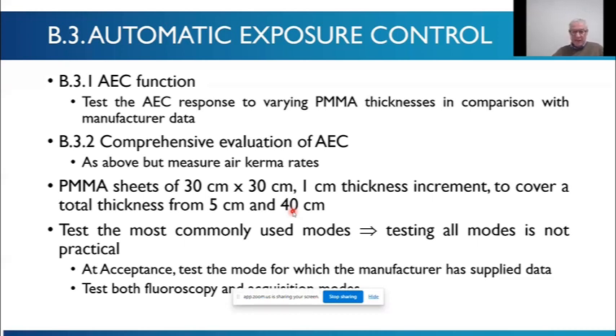When people do AECs, normally you think about 20 centimeters as your standard thickness. It's probably a bit too thin for a lot of imaging systems. This 20 centimeters certainly for interventional and cardio, it's closer probably to 30 centimeters as a standard thickness, and certainly even higher under some projections. But the aim is to test the most commonly used modes. You can't do all the modes. I mean, there'll be 50, 60, 70 modes on some systems or protocols. You can't do those. You need to know which are going to be commonly used, know which modes the manufacturers supply data for, and make this measurement.